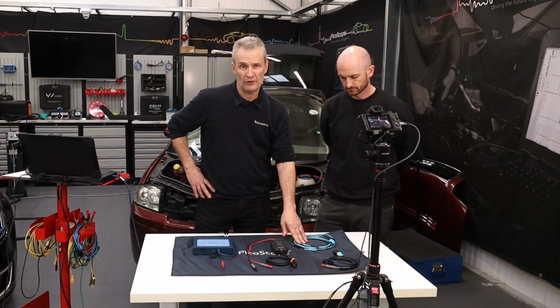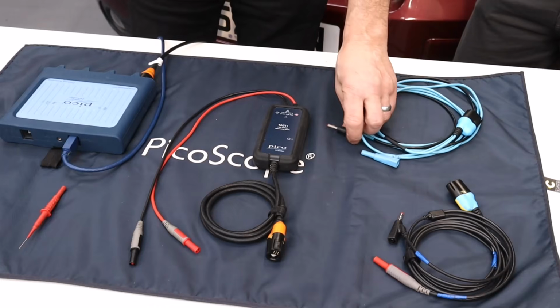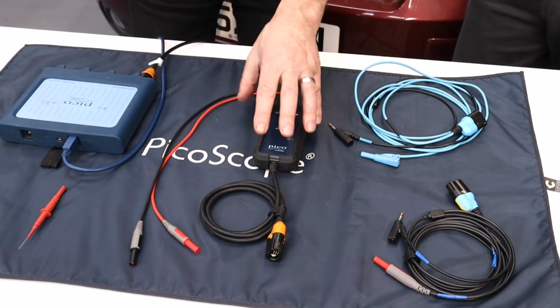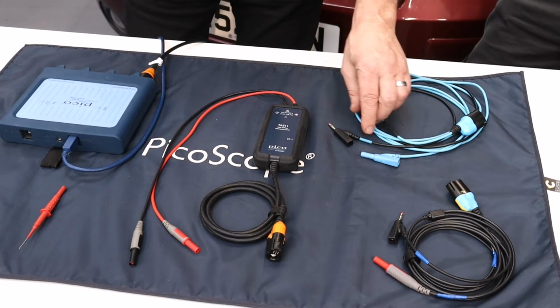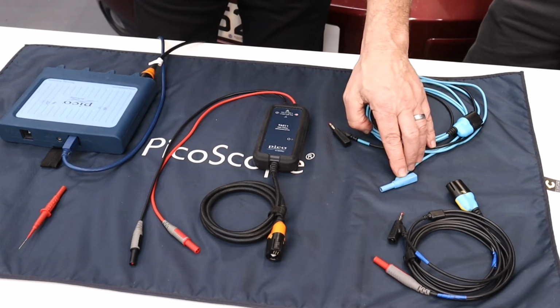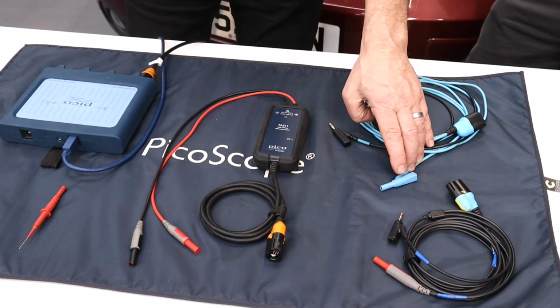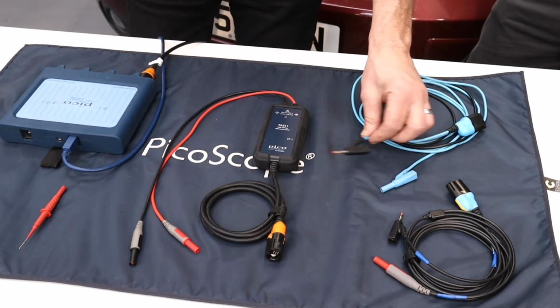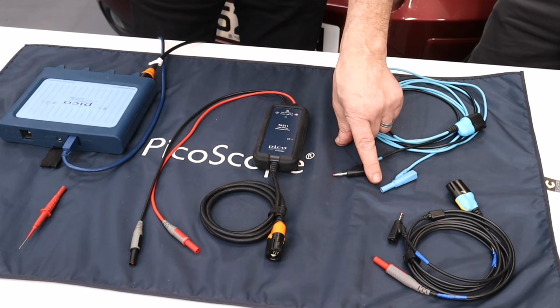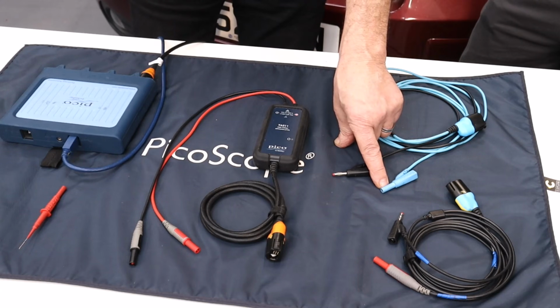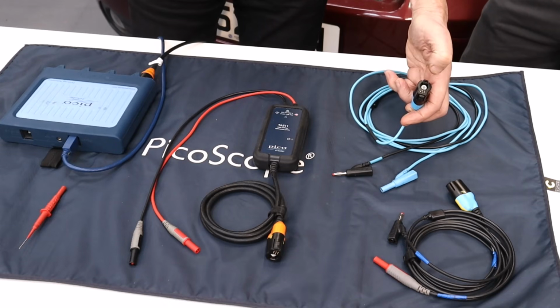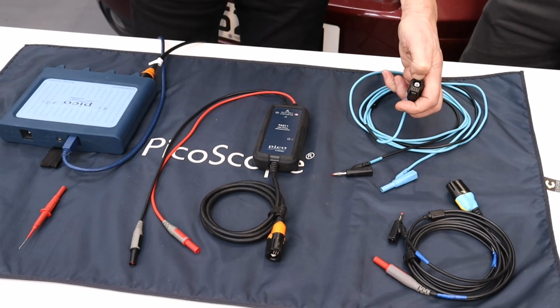Certainly this one is what we call a ×1 test lead. Of course you would carry this normally. This could be substituted for that, but either way. Here we've got a maximum of 200 volts. That's low energy, remember, and that's our ground lead. So if we were measuring 200 volts here, we would actually be measuring also 200 volts at this end, at the BNC end as well.